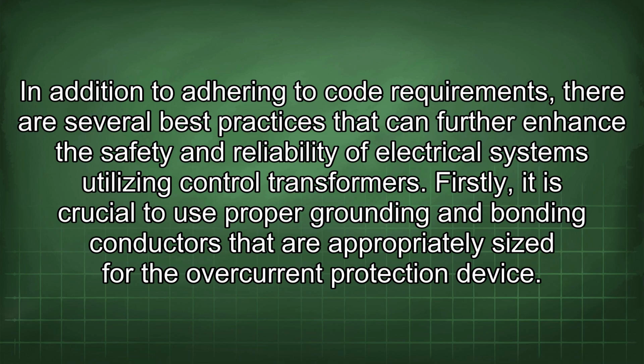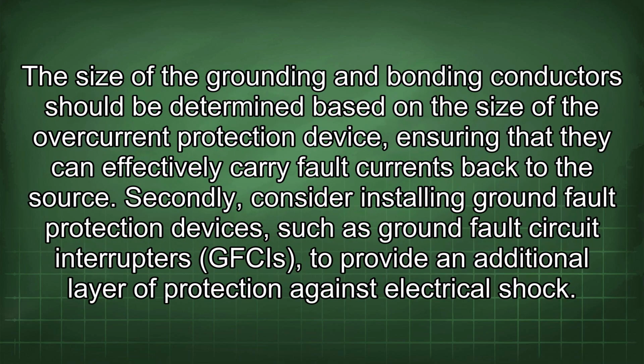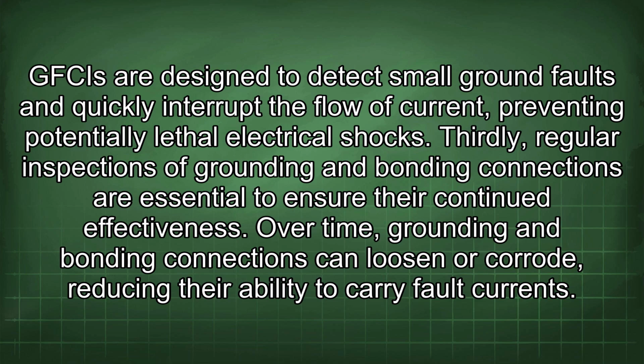Firstly, it is crucial to use proper grounding and bonding conductors that are appropriately sized for the overcurrent protection device. The size of the grounding and bonding conductors should be determined based on the size of the overcurrent protection device, ensuring that they can effectively carry fault currents back to the source. Secondly, consider installing ground fault protection devices, such as ground fault circuit interrupters (GFCIs), to provide an additional layer of protection against electrical shock. GFCIs are designed to detect small ground faults and quickly interrupt the flow of current, preventing potentially lethal electrical shocks.